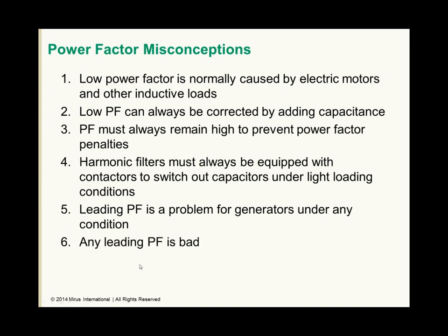And finally, it's just a simple statement that any leading power factor is bad. We often hear this from people, and a leading power factor can be useful in compensating for a low lagging power factor. Therefore, as long as we ensure that the capacitive reactive power is not too high, it is not always a bad thing.